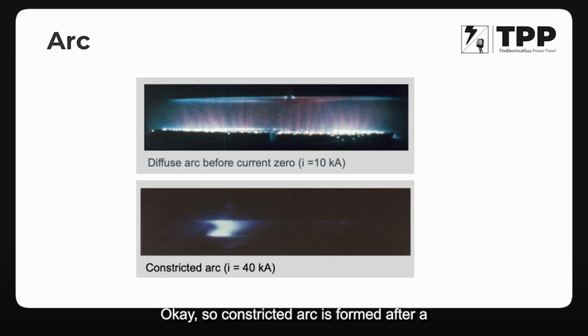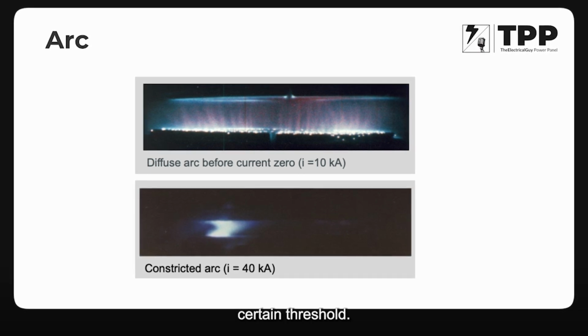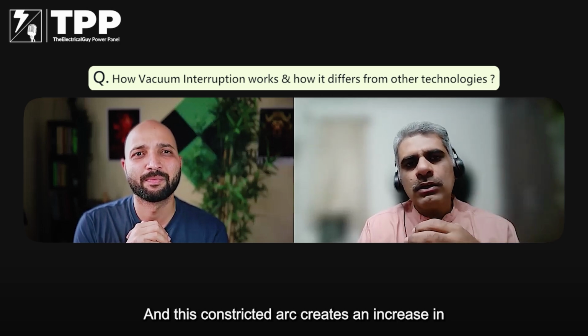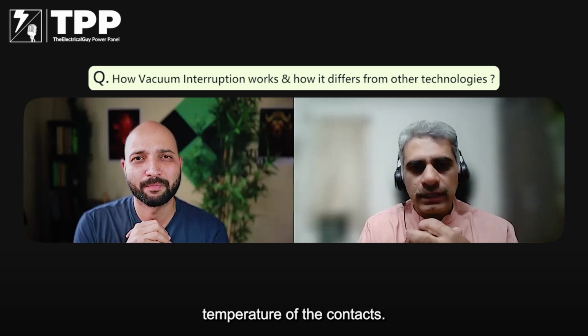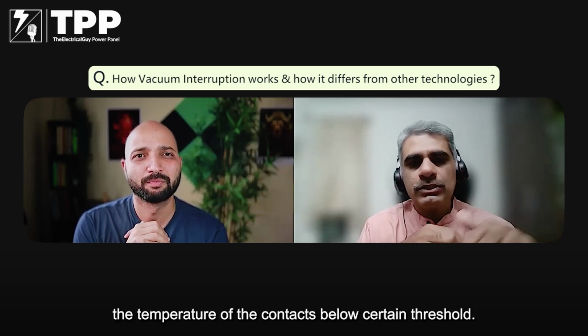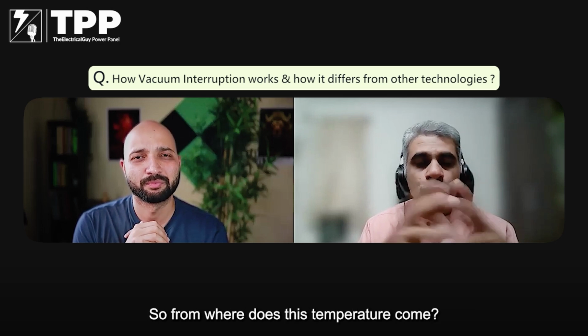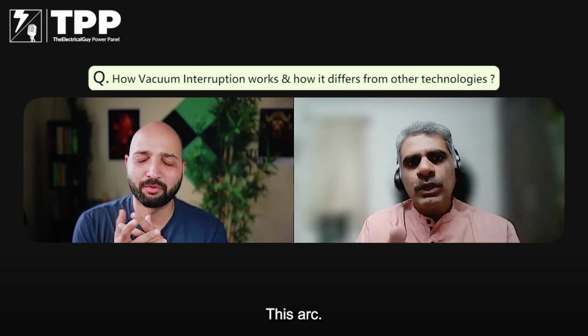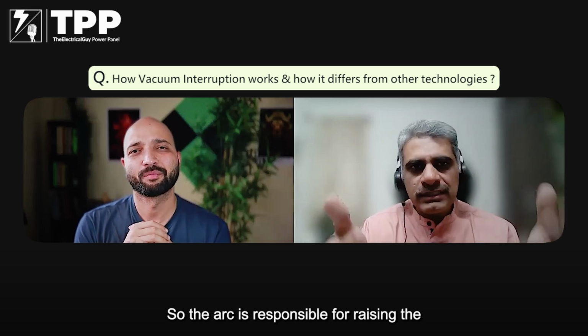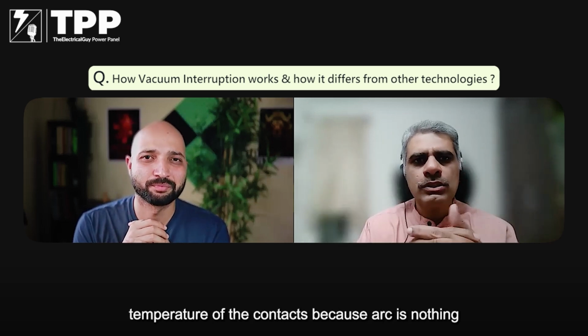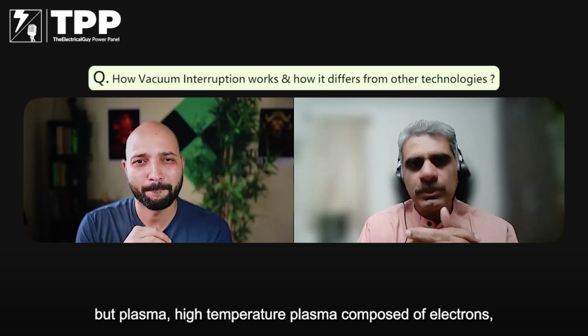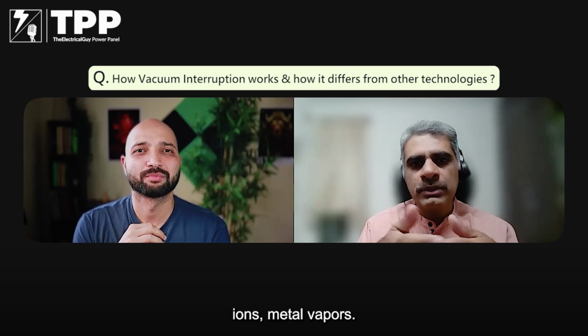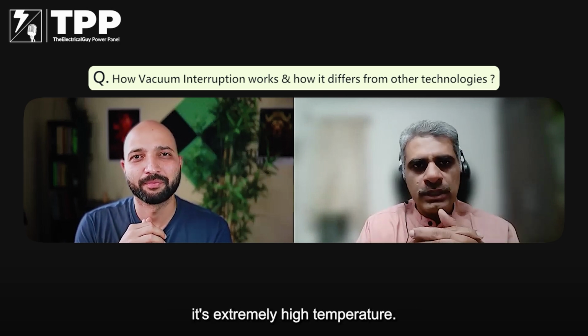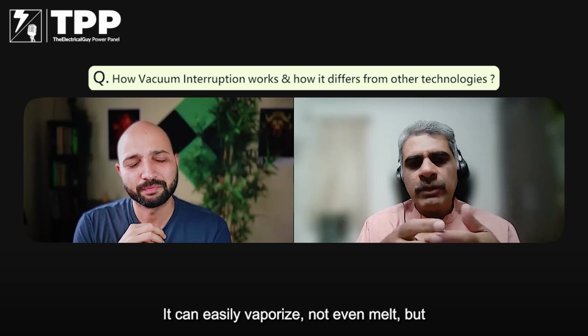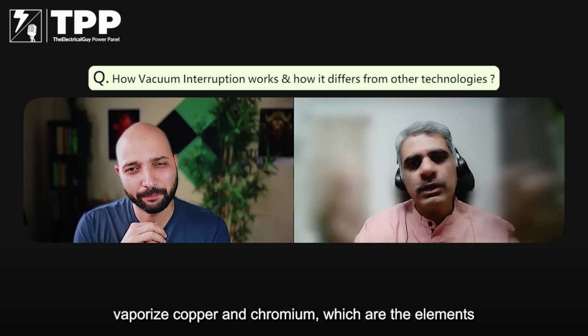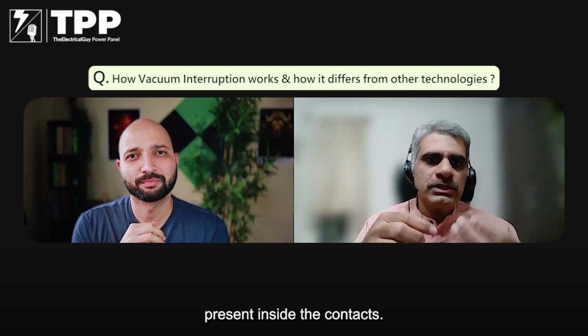Okay, so this constricted arc is formed after a certain threshold, and this constricted arc creates an increase in temperature of the contacts. So, as I said, we need to keep the temperature of the contacts below a certain threshold. So, from where does this temperature come? From the arc. The arc is responsible for raising the temperature of the contacts, because arc is nothing but plasma, high temperature plasma composed of electrons, ions, metal vapors. So it's a composition of all these, and it's extremely high temperature. It can easily vaporize, not even melt, but vaporize copper and chromium, which are the elements present inside the contacts.